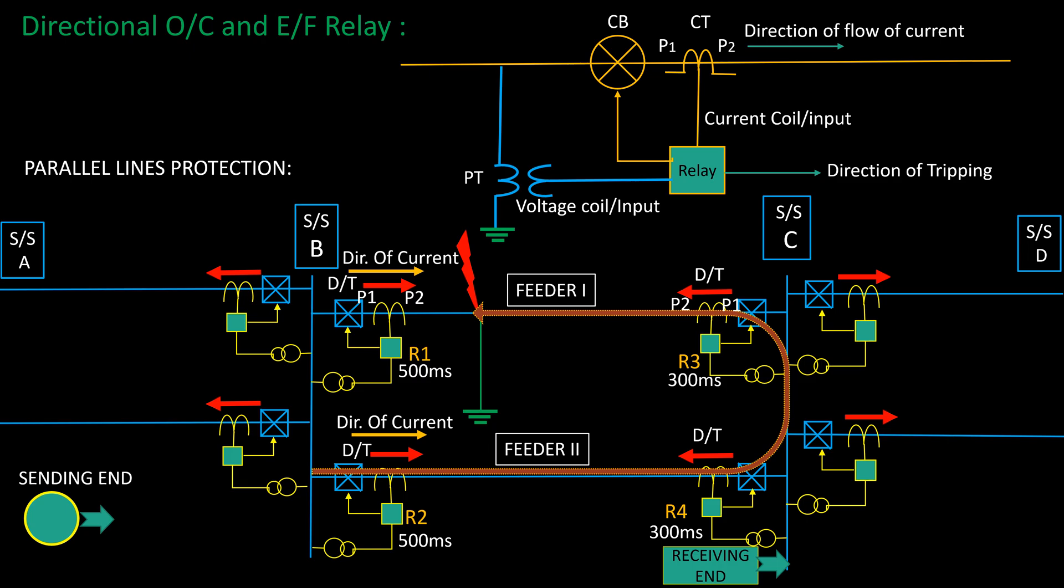This can be prevented by setting a more time discrimination at sending end relays with respect to receiving end. Therefore, time setting at relays R1 and R2 will be kept likely 500 milliseconds, and that of relays R3 and R4 is 300 milliseconds for such time discrimination.